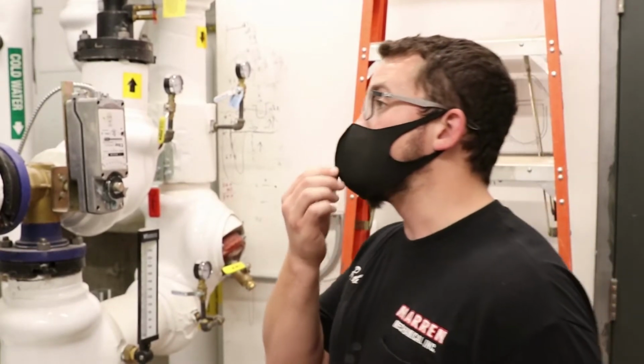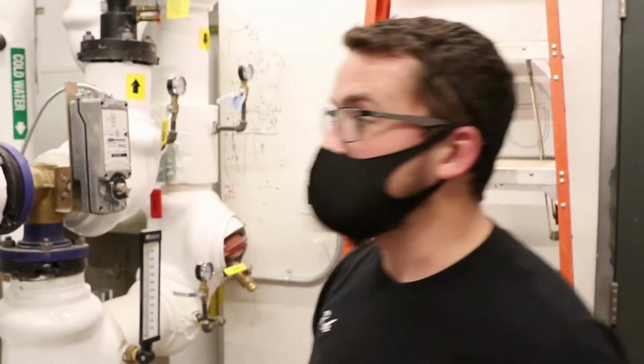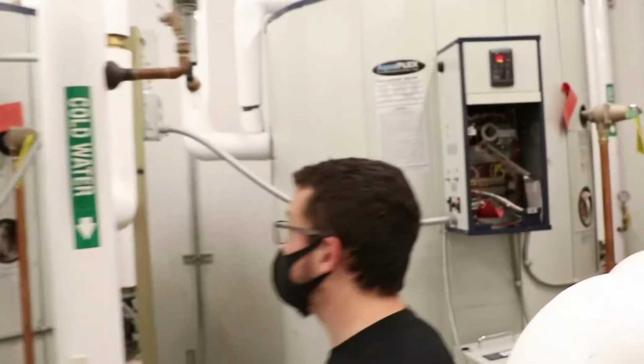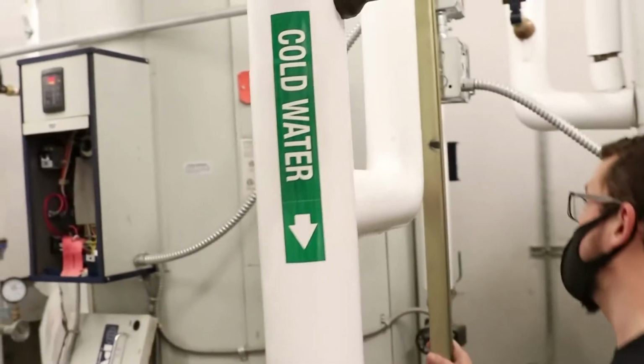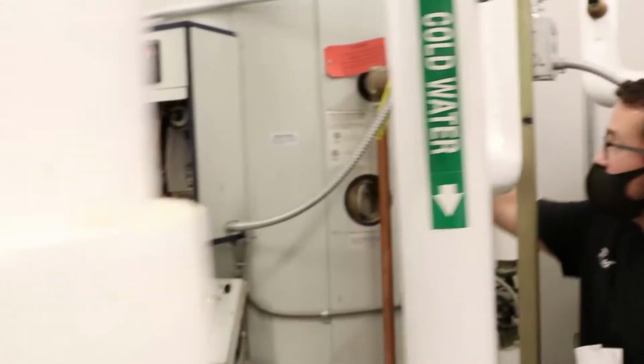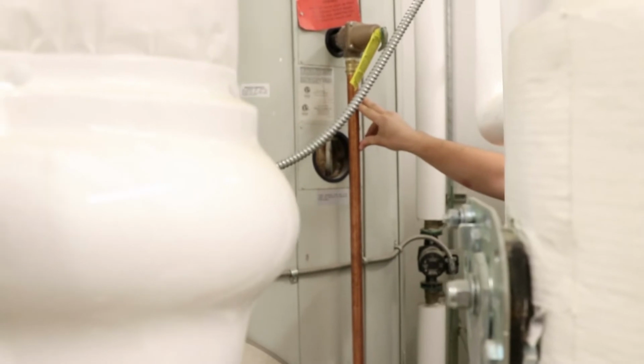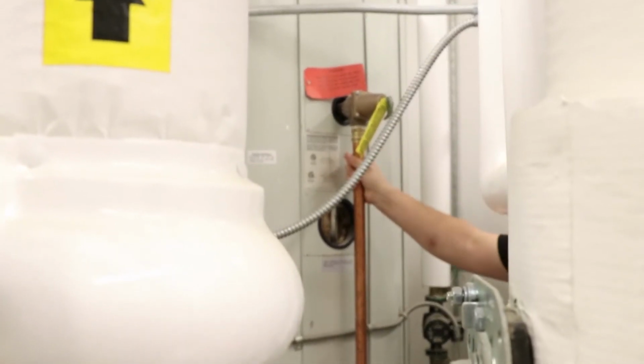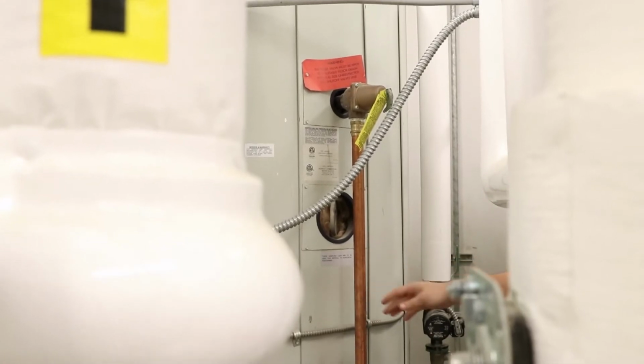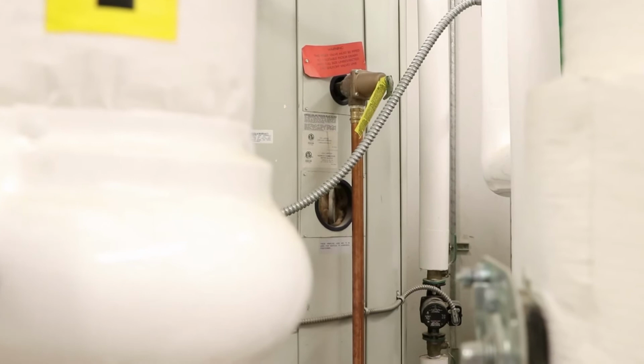Annually, the temperature and pressure relief valve should be tested. So this one's a little easier to read here. This relief valve is set to open and discharge water at either 150 psi or 210 degrees. They're a very important safety device. They can never be impeded or plugged or clogged or anything like that. And a very easy way to test them is annually.